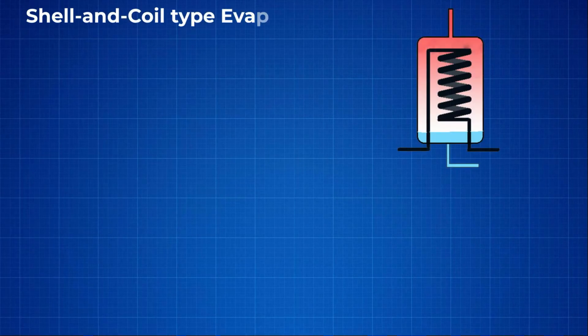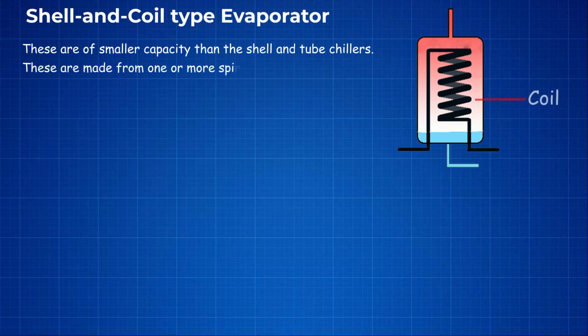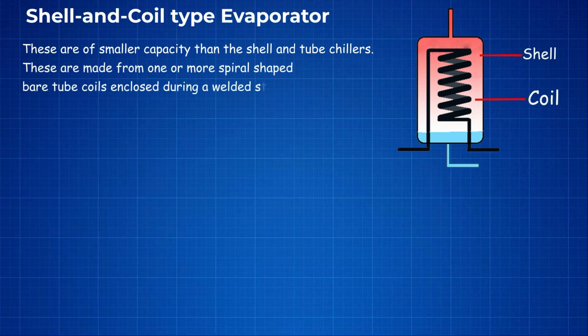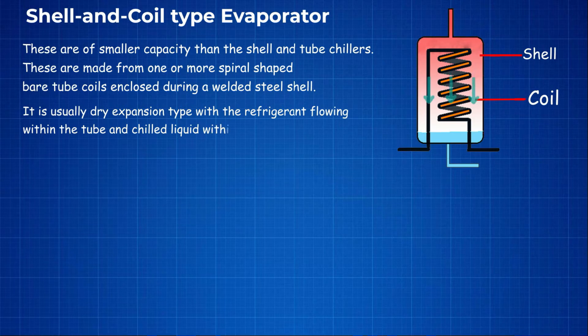Shell and coil type evaporators are of smaller capacity than the shell and tube chillers. These are made from one or more spiral shaped bare tube coils enclosed within a welded steel shell. It is usually a dry expansion type with refrigerant flowing within the tube and chilled liquid within the shell.